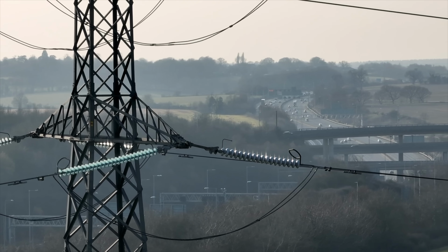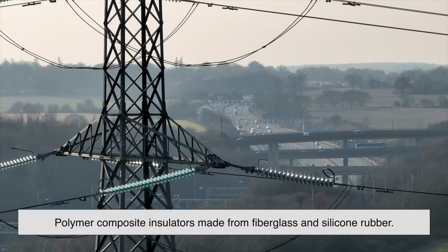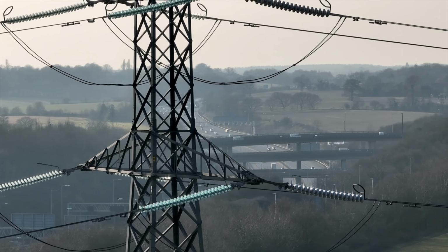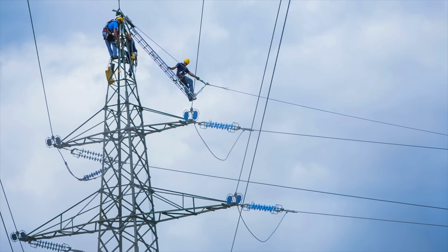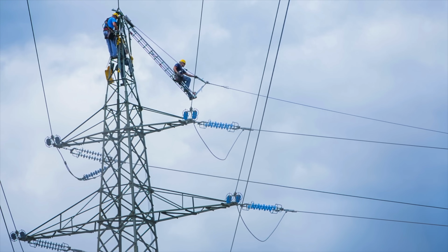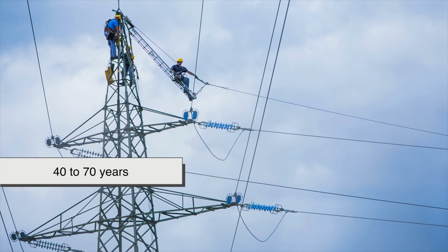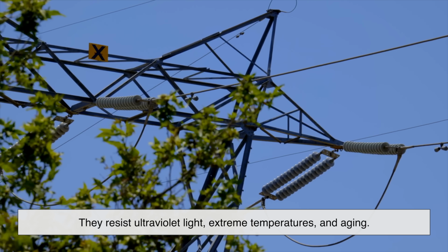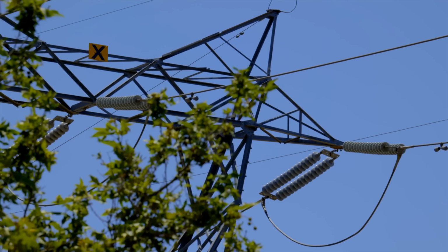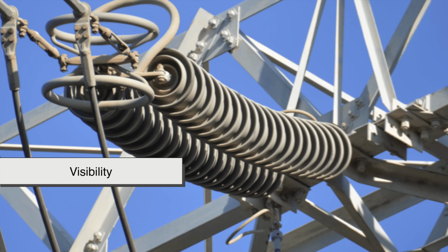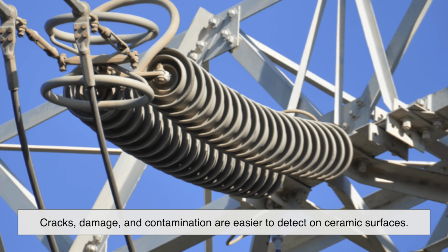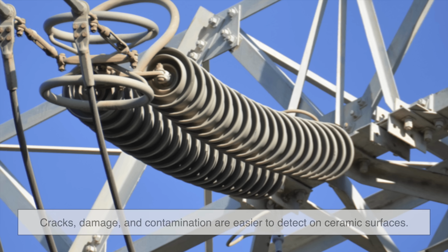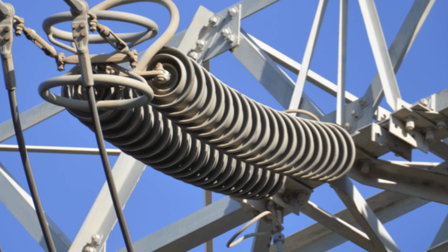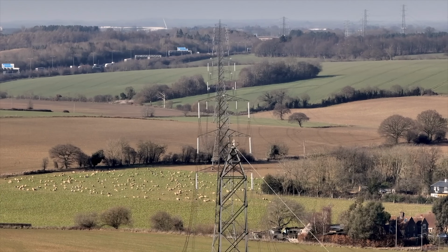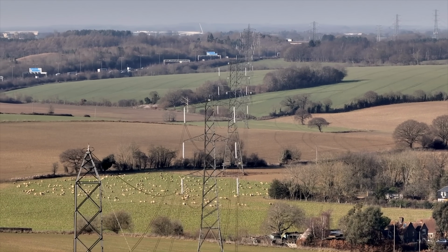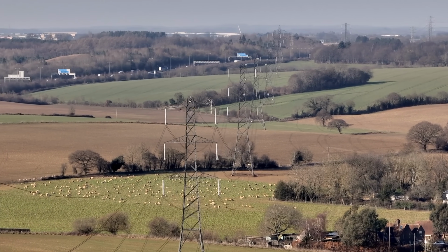Today, some power lines use polymer composite insulators made from fiberglass and silicone rubber. These are lighter and sometimes cheaper. However, ceramic disc insulators remain popular because of their proven lifespan, often 40 to 70 years. They resist ultraviolet light, extreme temperatures, and aging. Another advantage is visibility. Cracks, damage, and contamination are easier to detect on ceramic surfaces. This makes inspections more reliable, which is critical for high-voltage infrastructure. Even in a world of modern materials, disc insulators continue to be a trusted solution.